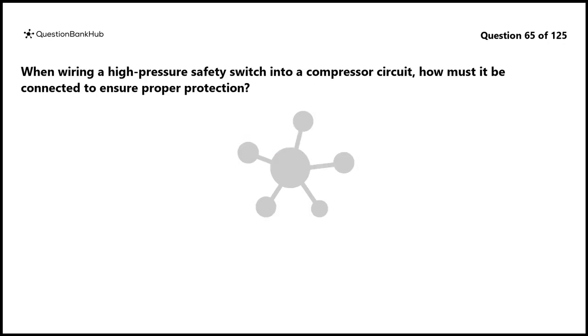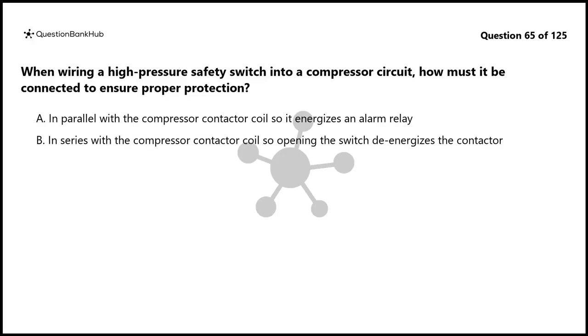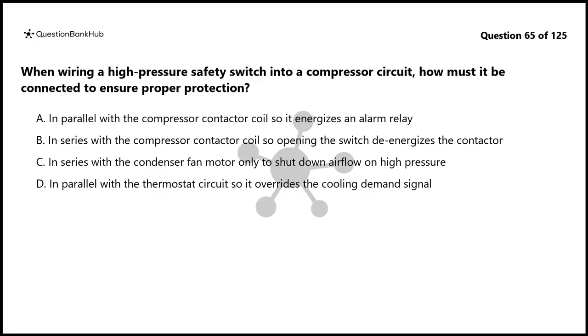Question 65. When wiring a high-pressure safety switch into a compressor circuit, how must it be connected to ensure proper protection? A. In parallel with the compressor contactor coil so it energizes an alarm relay. B. In series with the compressor contactor coil so opening the switch de-energizes the contactor. C. In series with the condenser fan motor only to shut down airflow on high pressure. D. In parallel with the thermostat circuit so it overrides the cooling demand signal.